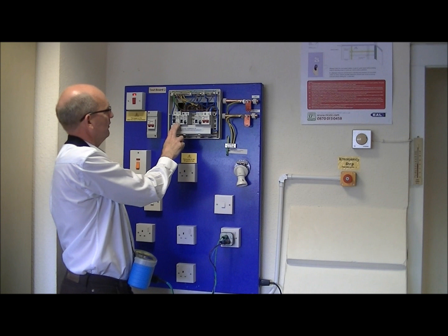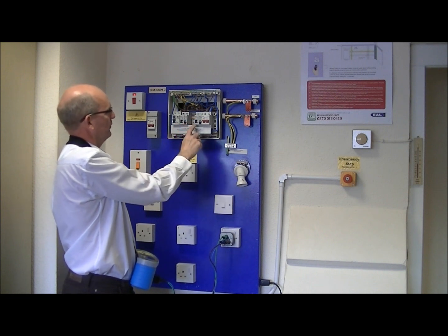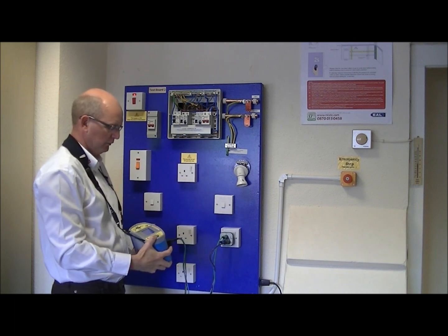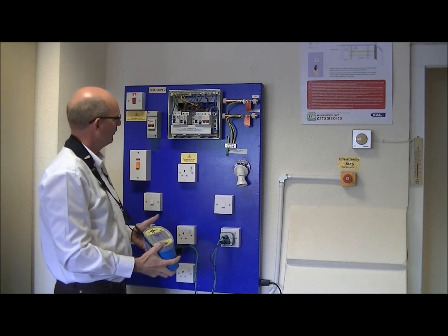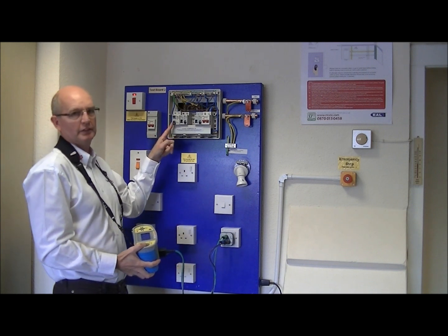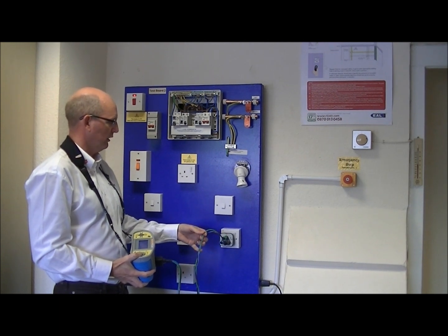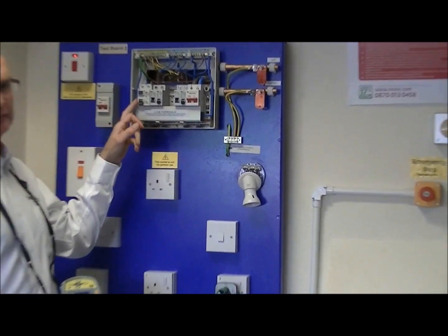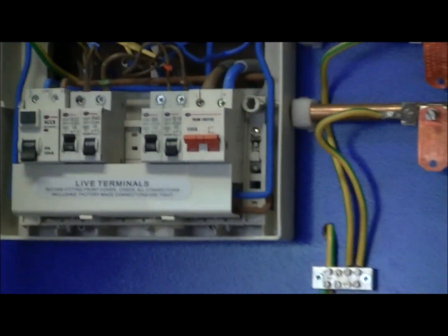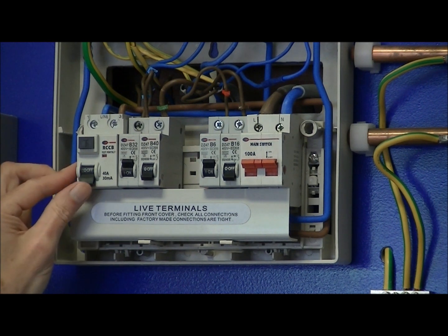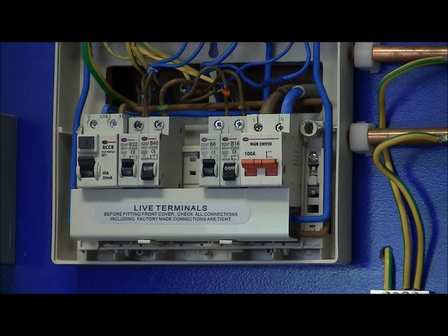Now the difference here is our lighting circuit was not protected by an RCD, whereas now it is. Now if we were to run the test now, I'll just demonstrate. It trips the RCD. The reason being is our meter is sending a test current down the earth CPC, and this is being picked up by the RCD. So with my meter, I put it on a less sensitive no trip setting so that I can re-enable the circuit with the RCD, rerun the test, and hopefully this time the RCD won't trip.